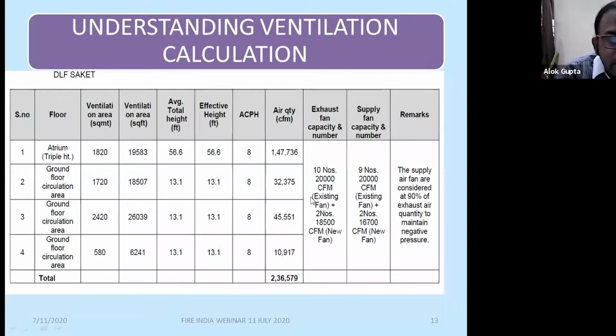These are simple multiplication calculations. Based on this, we have calculated around 10 existing fans of 20,000 CFM. These are the existing fans which are already there, plus some additional fans. You can see that the supply fans are considered around 10% negative pressure we have maintained. That means in case of fire, more exhaust can be taken in less time.